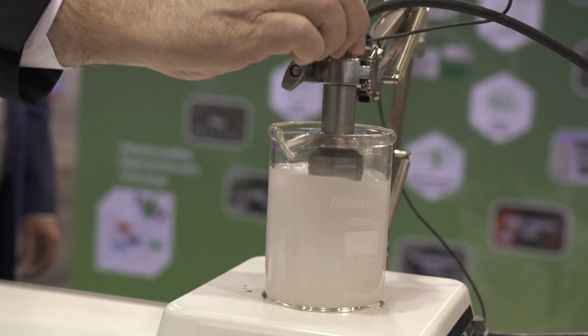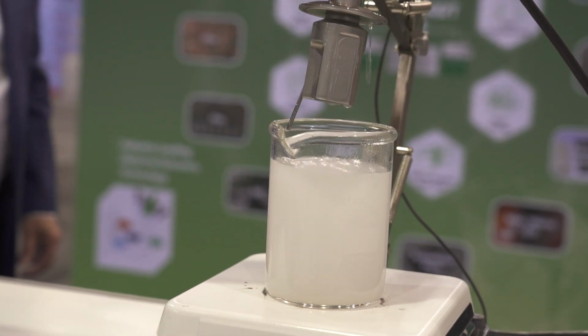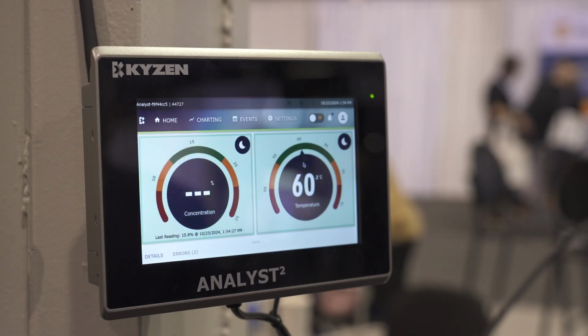If your concentration starts to drift down just a little bit, at the end of the day, I'll make an adjustment. I'll be ready for tomorrow. I'm still within my control limits. Well, it's very easy. It's very intuitive, it's got a traffic light system there. Well, that's right. It's green because things are good. If we were to lift this up very quickly here for a second, once we get it out of there, lo and behold, it doesn't have a signal, so it doesn't know what it is.